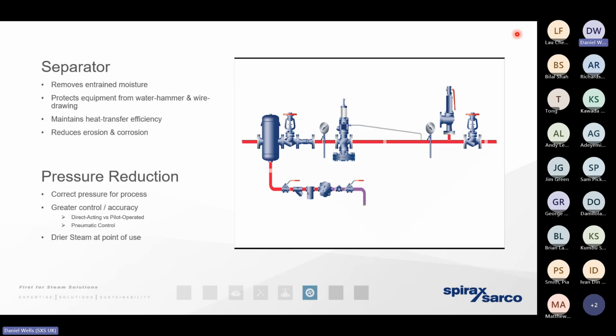So something else that we need to give thought to is getting the moisture away from the steam. By removing the moisture, we're going to have drier steam with more energy in it. We're going to have drier steam carrying less moisture, so we've minimized the risk of erosion. So we use a steam separator at this point. The steam separator allows that moisture to break away from the steam that it is carried by. The condensed moisture is then taken away across a steam trap, and the dry steam then continues towards the process. So we've protected that capital equipment from the risk of erosion, and we've now got a nice high energy content that means the process is going to take place more rapidly or efficiently.